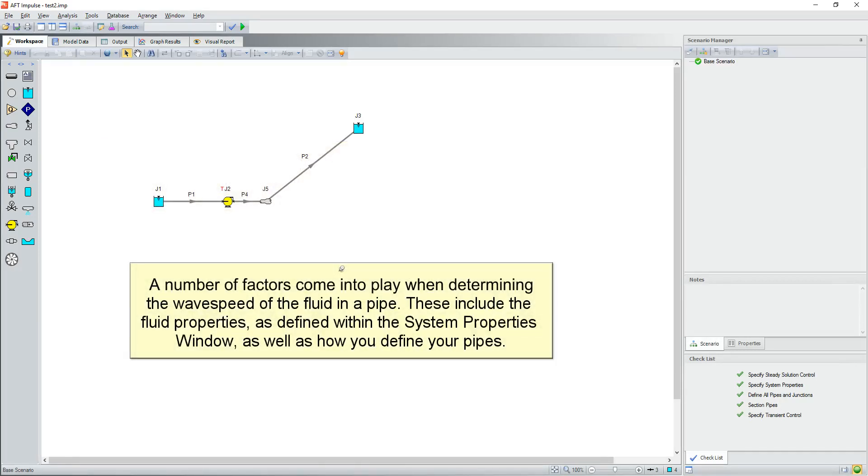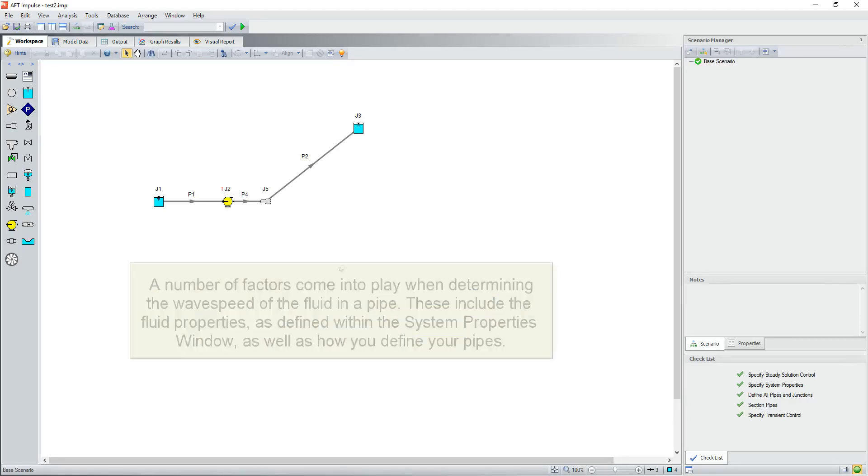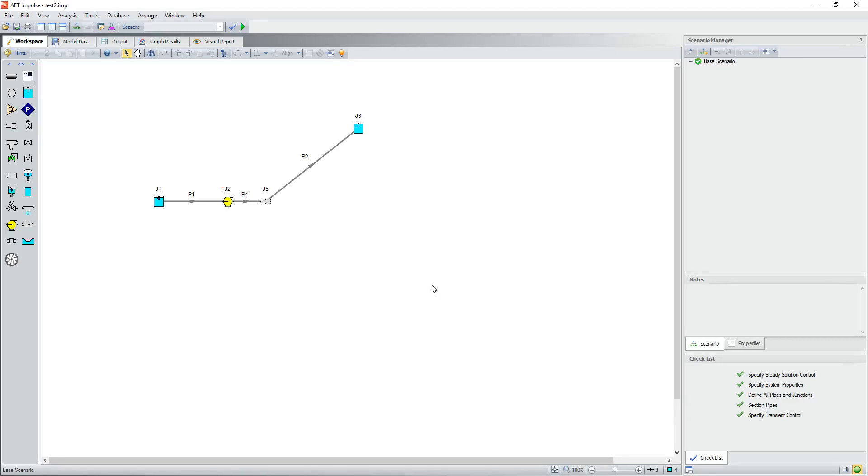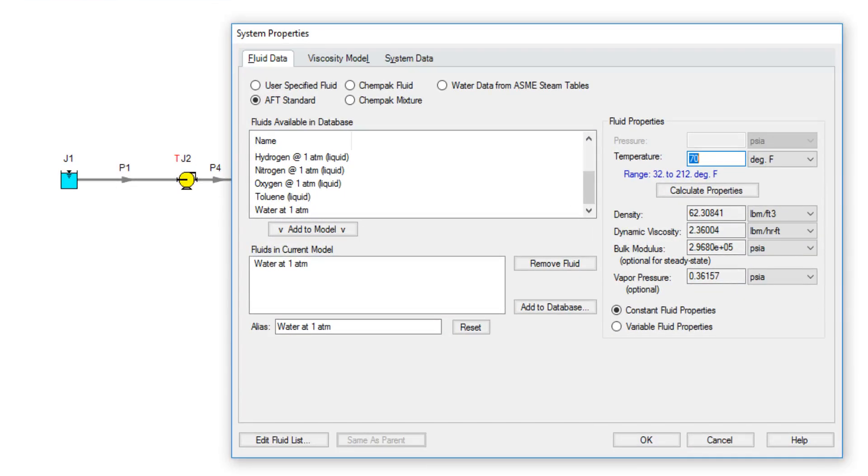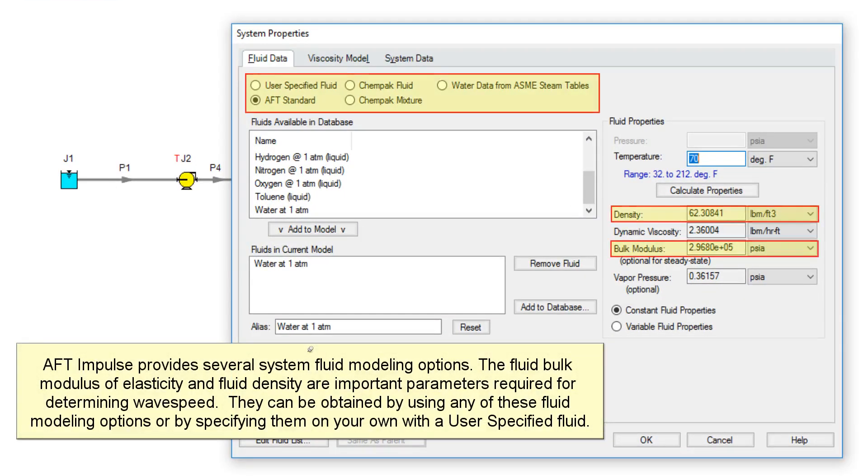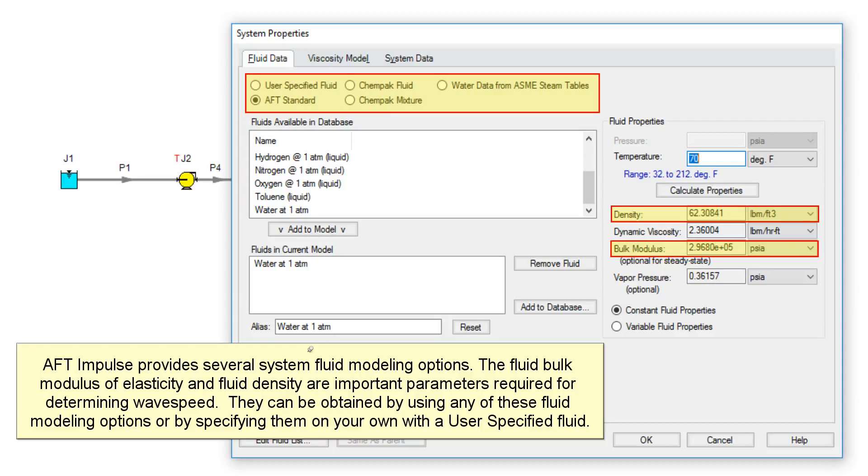A number of factors come into play when determining the wave speed of the fluid in a pipe. These include the fluid properties as defined within the system properties window, as well as how you define your pipes. AFT Impulse provides several system fluid modeling options. The fluid bulk modulus of elasticity and fluid density are important parameters required for determining wave speed. They can be obtained by using any of these fluid modeling options, or by specifying them on your own with a user specified fluid.